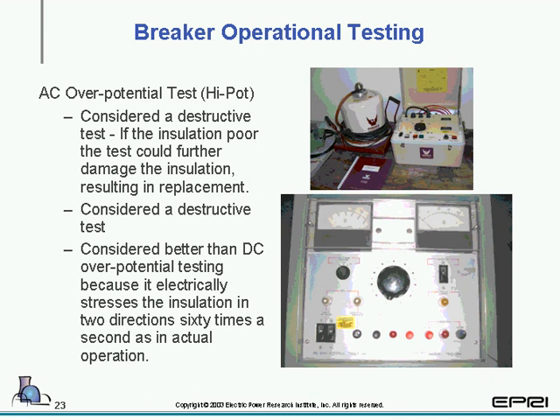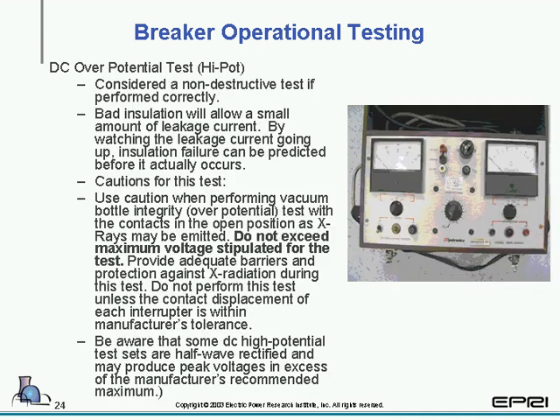A little more on AC hi-pot testing. Some particular AC units actually use a pulsating AC or a square wave, so that the wave is not true. It's considered destructive, but is also considered better than DC. One of the main reasons is that it stresses the insulation in two directions, 60 times a second, and is more of the real world of what the piece of equipment is going to see.